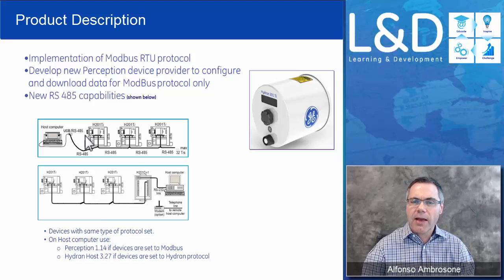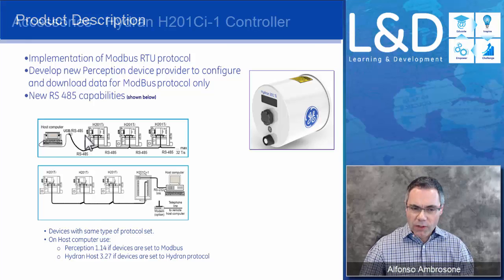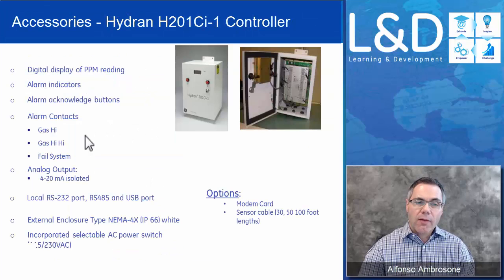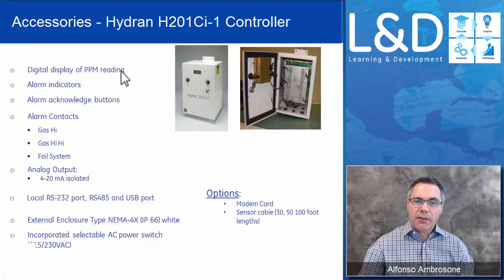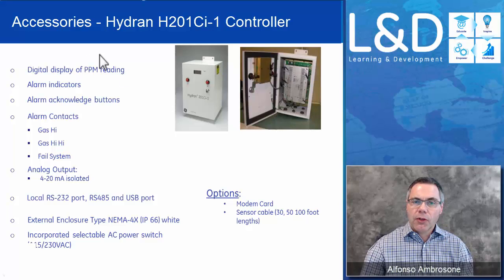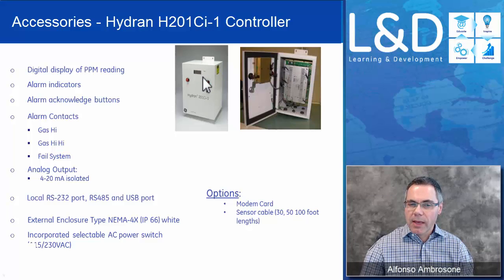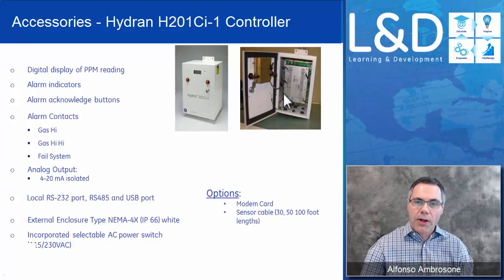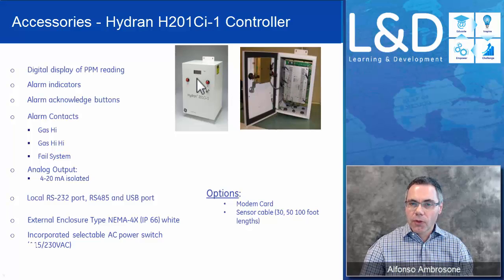We also have accessories for this equipment. We have two controllers. The CI1 controller is an extension of the Ti. If you have a Ti mounted on an upper filling valve where you can't easily see the display, you can bring the signal back to a CI1 controller and have a local display of the PPM. It also has alarm lights and all the relay and communication options, so you don't have to wire up the Ti directly. The only thing this box will not show on the display is the trend — it just shows the PPM level.